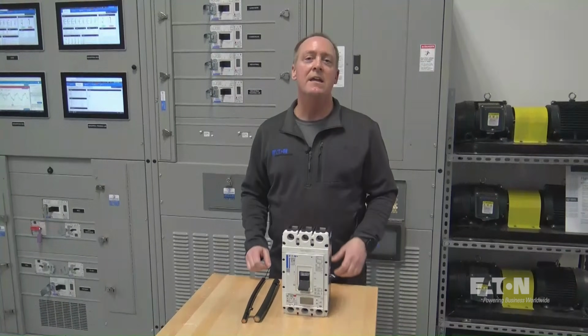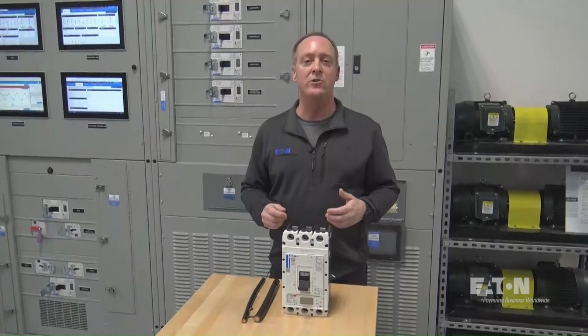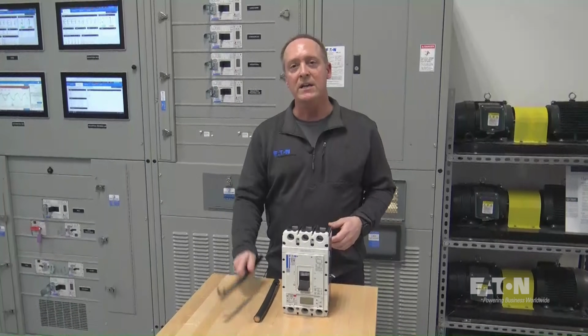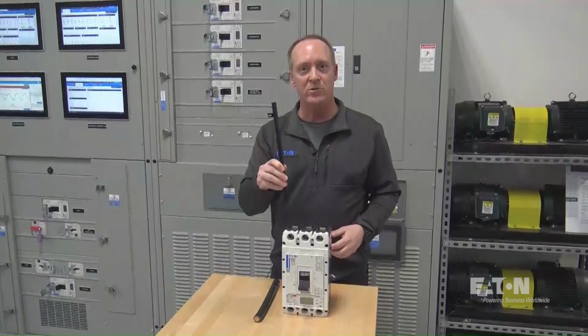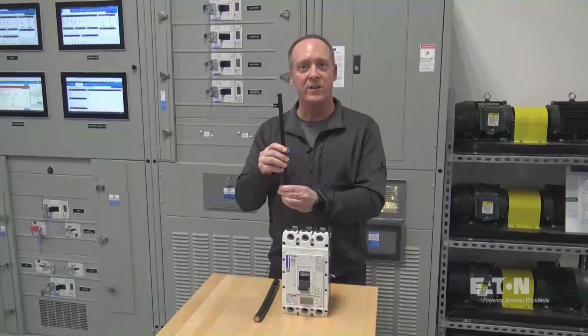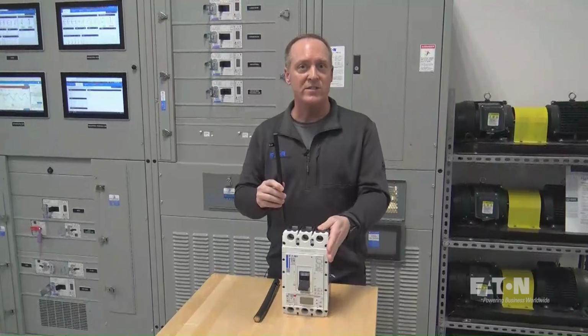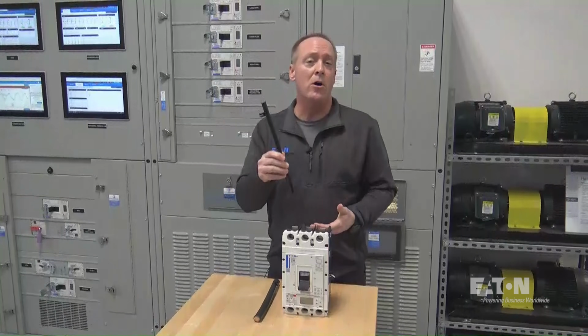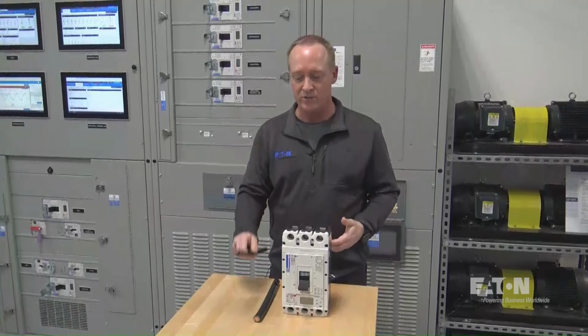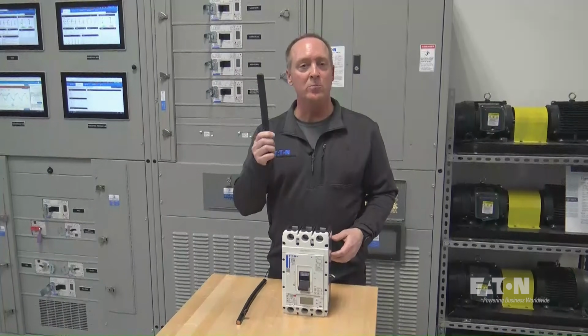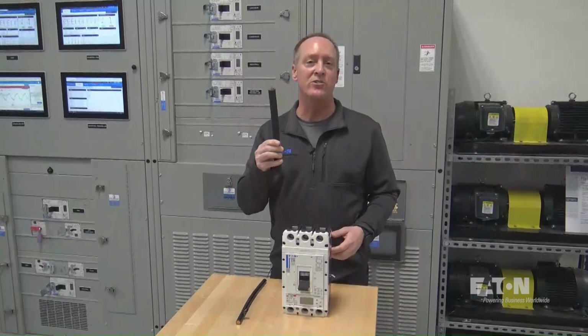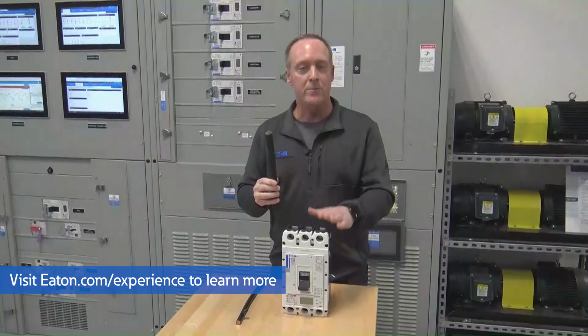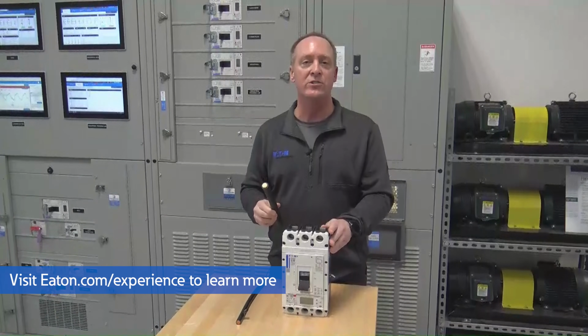breaker. In summary, it only makes sense to use a 100% rated circuit breaker if you're going to take advantage of the smaller cable sizing. That less expensive cable, paired with the more expensive 100% rated circuit breaker, can often represent significant cost savings. If you're going to size the cable per the standard 125% of its rated load, there is no benefit to using a 100% rated circuit breaker.